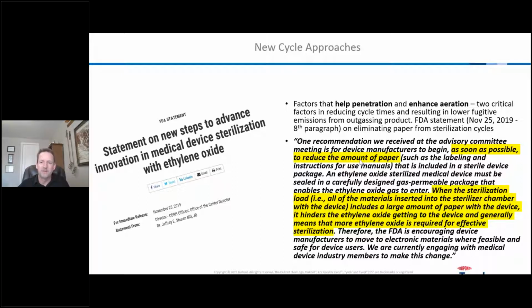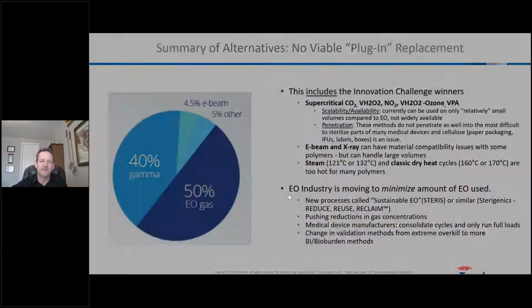Paper a lot of times will absorb EO, so in some cases it's going to require more ethylene oxide. It's going to absorb more of that, so there's less available to the product, and you have to use more ethylene oxide. That was one of the things the FDA looked at to make that change.